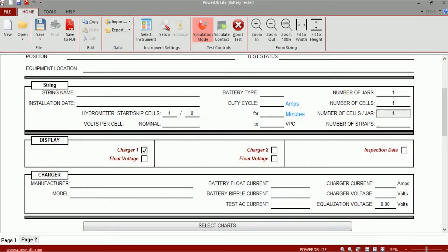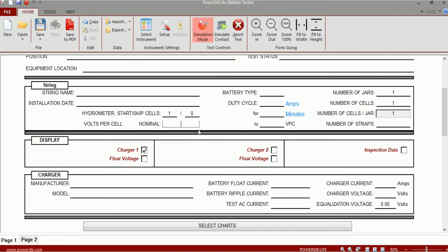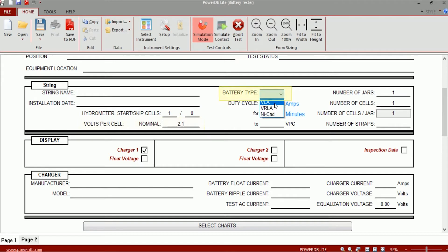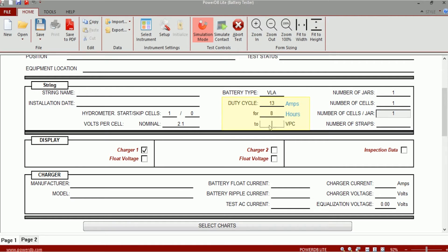On the impedance test form you would start by entering information about the battery string under test. You would enter the name assigned to the battery string, the installation date, and the nominal cell voltage. You can choose among three battery types. I'm going to choose vented lead acid. You can enter information about the duty cycle of the battery. So if my battery string is capable of providing 13 amps for a period of eight hours to an end cell voltage of 1.75 volts per cell, I would enter the information in this manner.